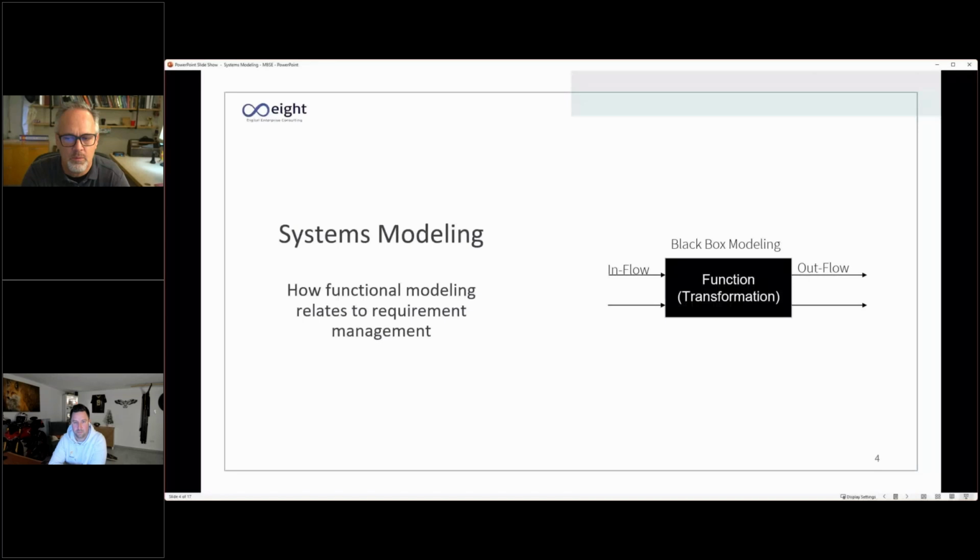And I think one of the problems that we run into is that when people do that, essentially they sit down with a Word document and just start writing what they believe the device needs to deliver. There's no methodology that they're using for development of those requirements, so therefore they don't know when to finish.